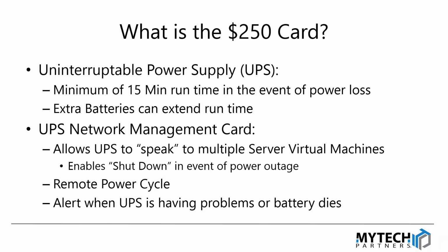So first of all, one of the minimum requirements that we recommend for our customers is that they have a UPS that, if you put all the devices connected to that UPS that you want to be power protected, which is typically everything in the server closet, and sometimes your phone system might be on a separate UPS, but all of your technology in the server room or data closet, in the event of a power outage, the battery, based on the power draw of all the equipment on that UPS, can sustain that equipment for up to 15 minutes. That is roughly our minimum requirement.